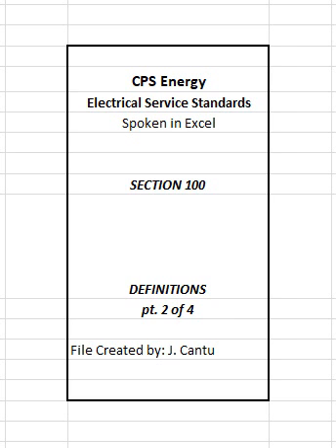Kilovolt amperes reactive, kVAR. The product of the voltage and the amperage required to excite inductive circuits. It is associated with the reactive power which flows between parallel generator windings and between generators and load windings that supply the magnetizing currents necessary in the operation of transformers, motors, and other electromagnetic loads. Reactive power does not load the generator set's engine but does limit the generator thermally.